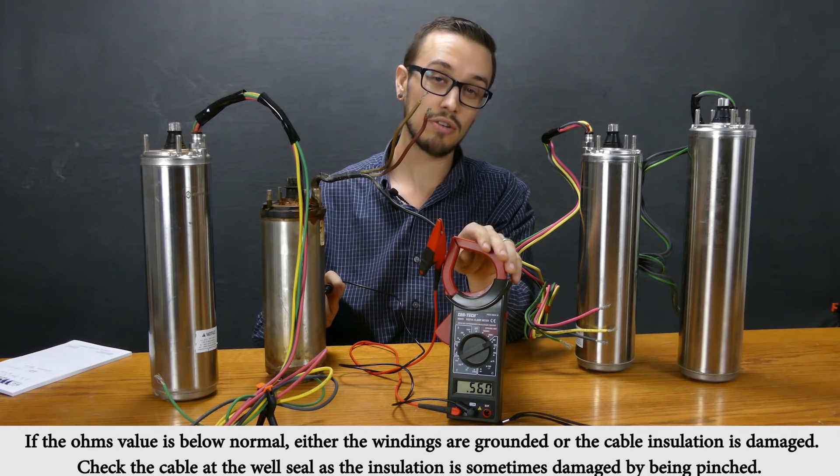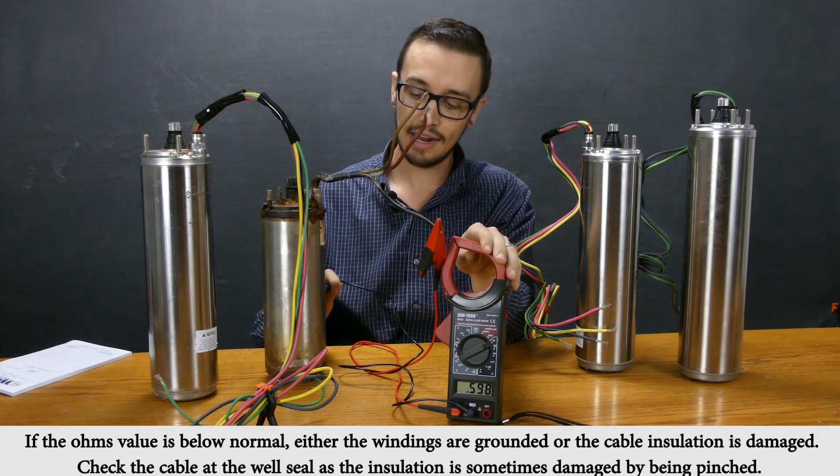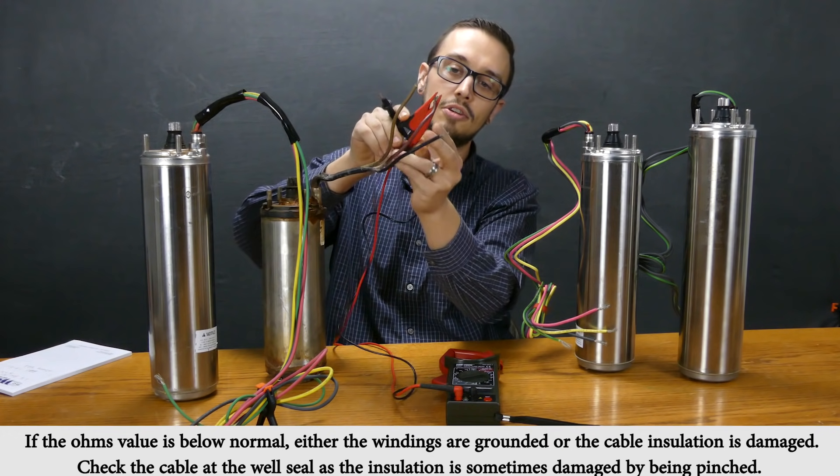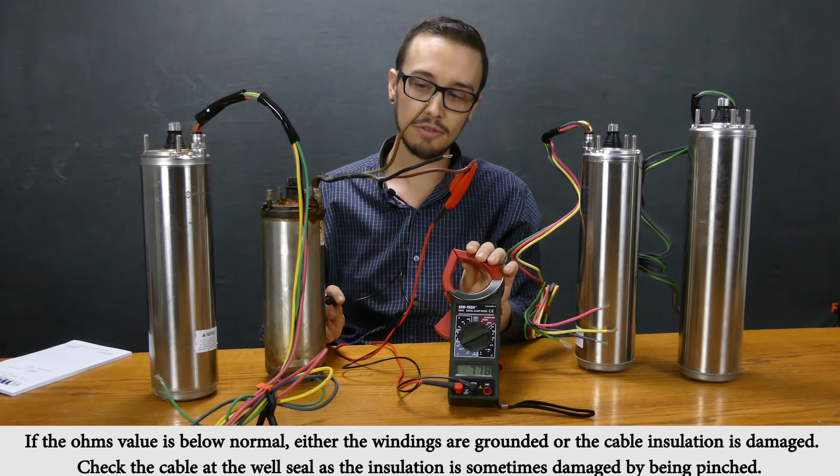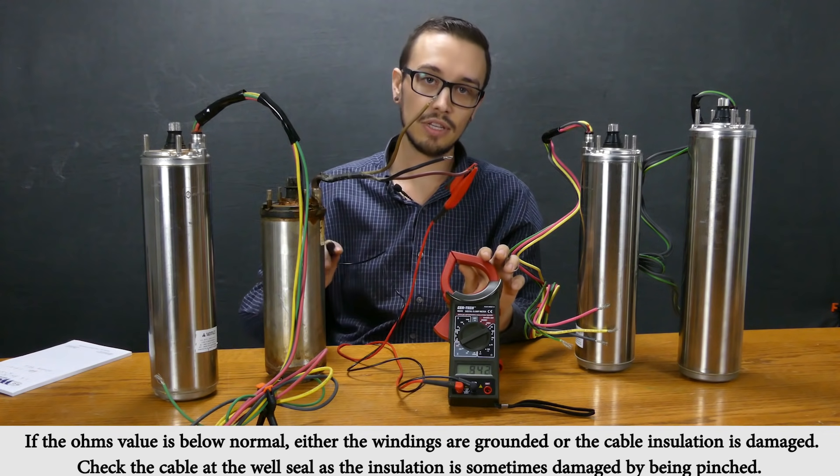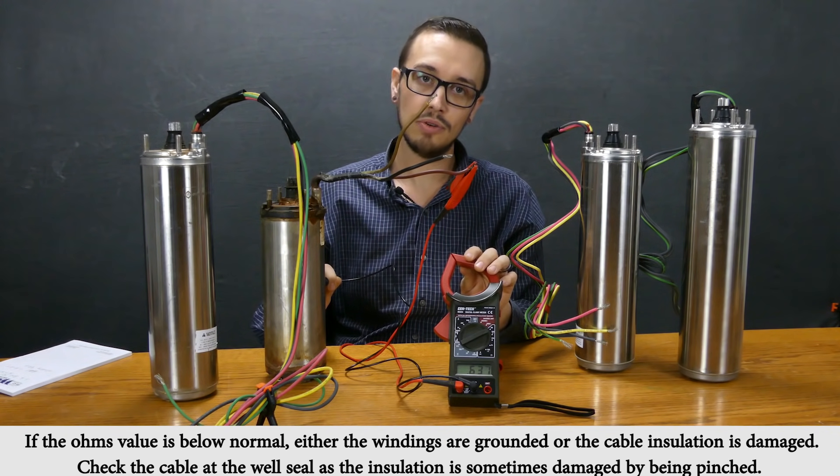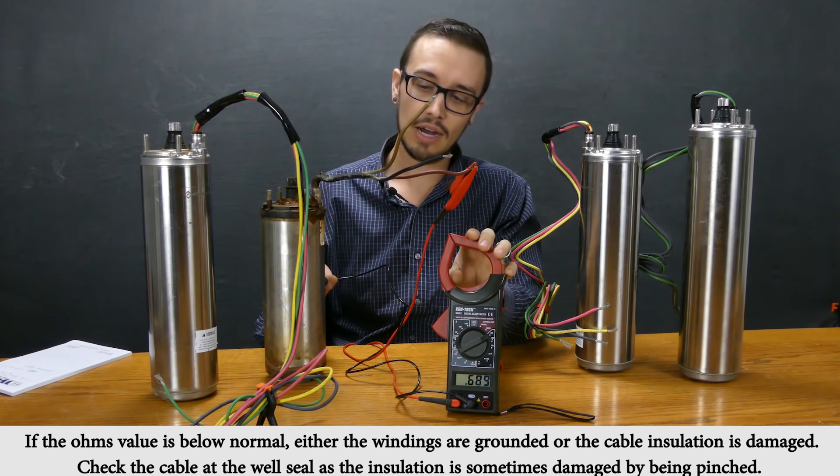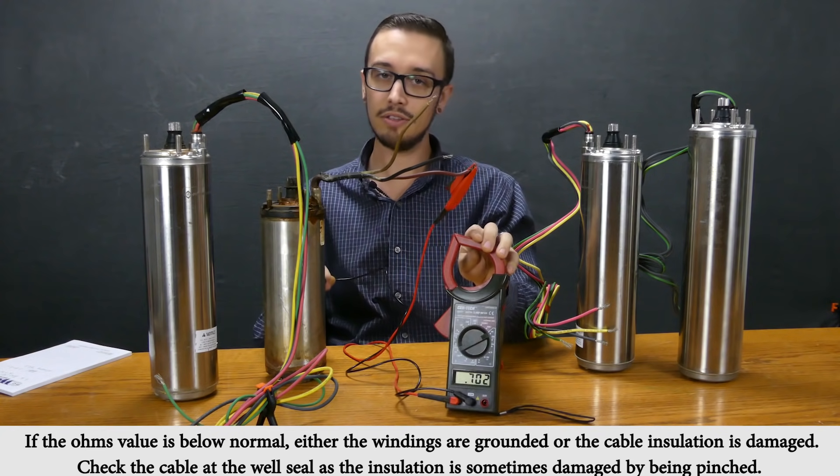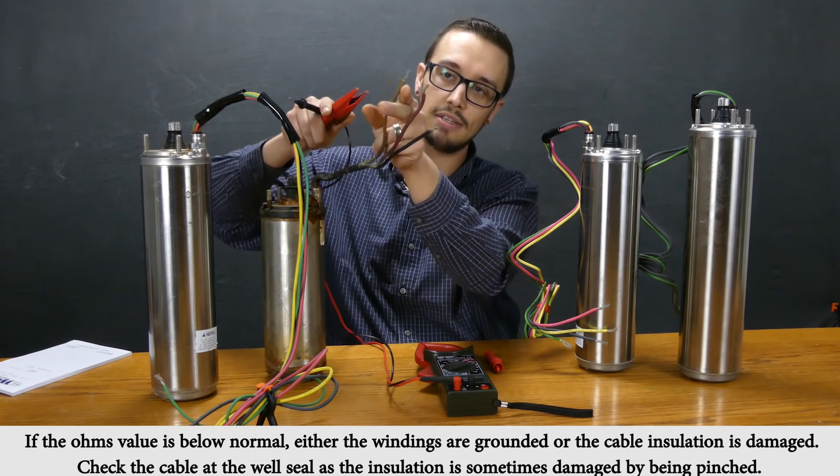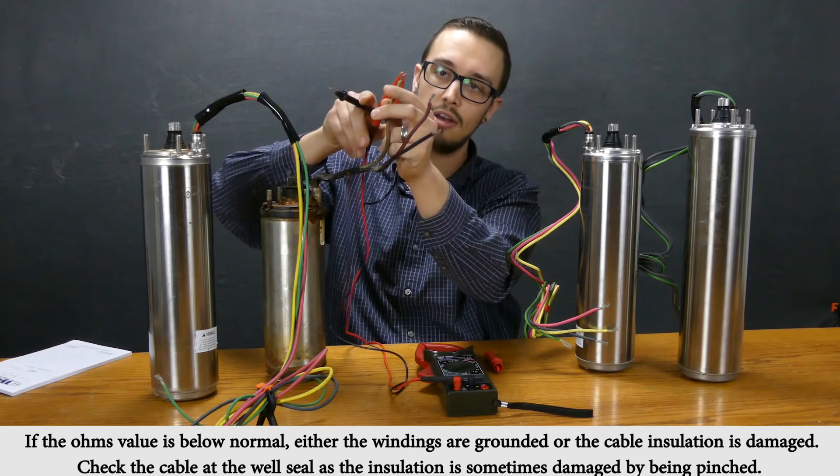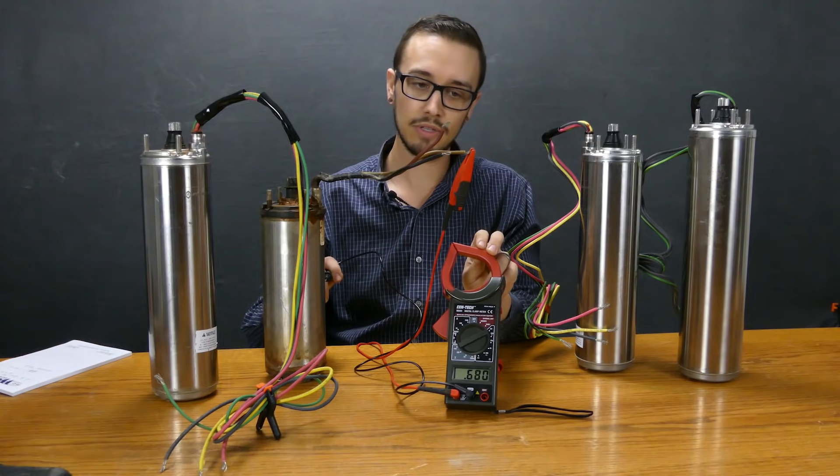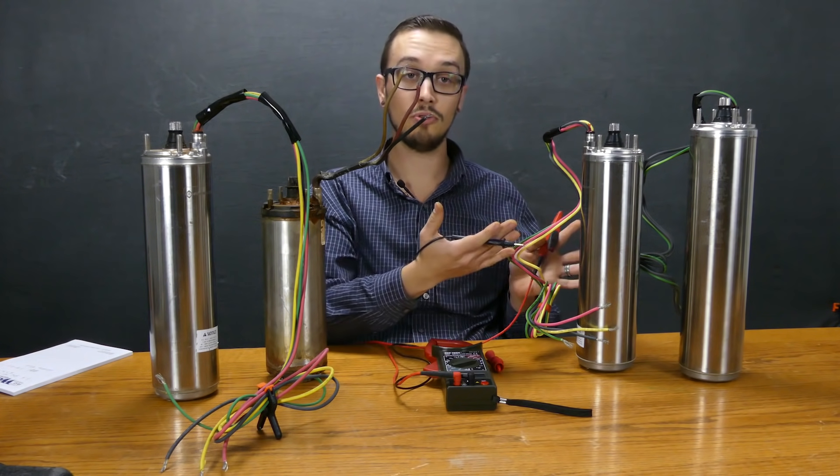That's indicating that we've got a short to ground. You can see that we're no longer in that high reading anymore. That's going to generally be the case on all of the different ones that you test because internally this is all connected. Without getting too in detail on how that works, they're all connected. So once you have a short to ground you should be able to read it essentially on all of the leads in most cases, but not necessarily every case. But in this case we can see it on all three different ones.